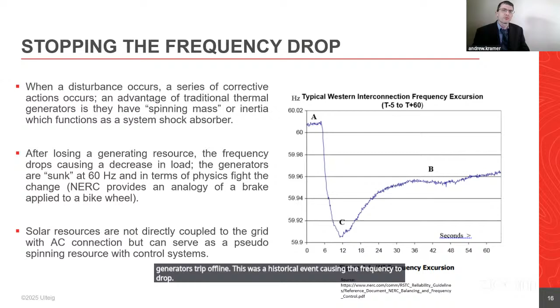So here's an example of what actually happens. This is, again, all from NERC. Within seconds after the disturbance occurs, the physical devices on the generator called governors sense the drop in frequency. They're not necessarily a fully intelligent control device, but they pick it up and work to bring up the generator's speed to start stabilizing the frequency loss. They don't restore it, they stabilize it. Within minutes, the generators raise their output based upon the supervisory control and data acquisition, that's SCADA, in terms of the AGC, automatic generation control. So what you're seeing here from A to C is the drop where the governors catch it, and then C to B is when the automatic generation control is telling the generators to pick their speed up and get that speed back up to the point where we can start restoring that frequency. There's a recovery period that typically goes into the minutes. A lot of the time, what happens is you don't have enough generators online and we need to call in the reserves.